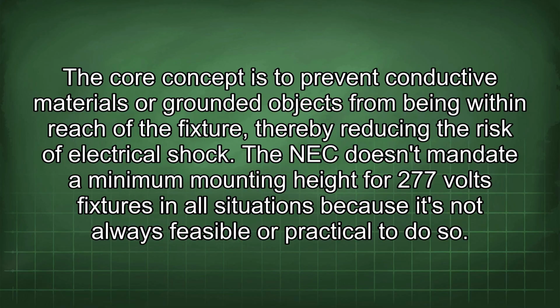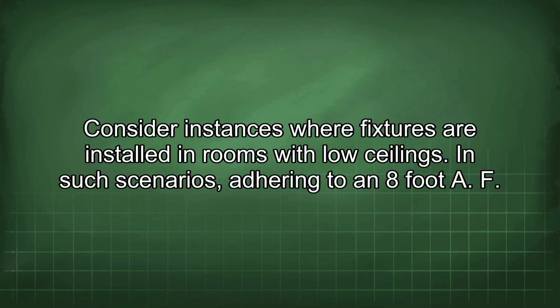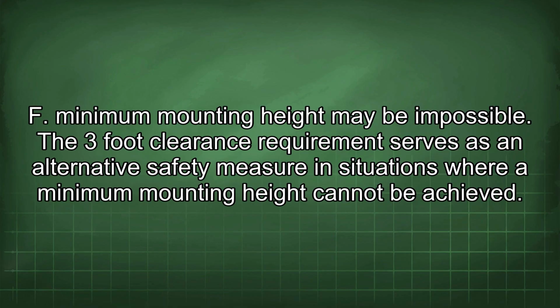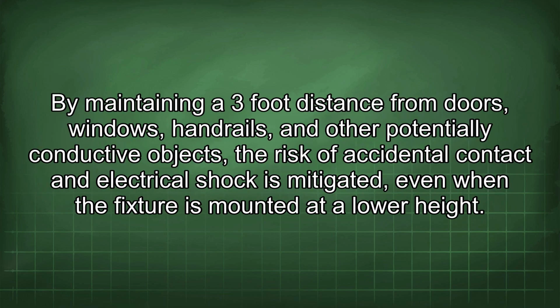The NEC doesn't mandate a minimum mounting height for 277 volt fixtures in all situations because it's not always feasible or practical to do so. Consider instances where fixtures are installed in rooms with low ceilings. In such scenarios, adhering to an 8-foot A.F.F. minimum mounting height may be impossible. The 3-foot clearance requirement serves as an alternative safety measure in situations where a minimum mounting height cannot be achieved. By maintaining a 3-foot distance from doors, windows, handrails, and other potentially conductive objects, the risk of accidental contact and electrical shock is mitigated, even when the fixture is mounted at a lower height.